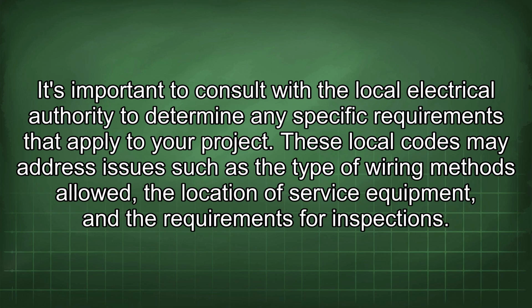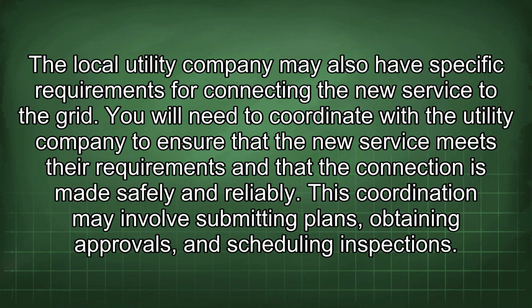These local codes may address issues such as the type of wiring methods allowed, the location of service equipment, and the requirements for inspections. The local utility company may also have specific requirements for connecting the new service to the grid. You will need to coordinate with the utility company to ensure that the new service meets their requirements and that the connection is made safely and reliably.